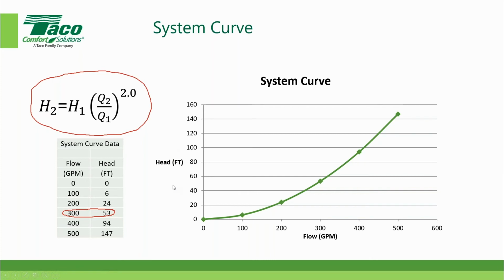If I plot that, I start with my design operating point, the 300 gallons per minute at 53 feet. I use this equation in the upper left-hand corner, I create the table, and then I just plug in these values, and I wind up with this curve, which is called the system curve. In our example, the system is a closed loop pressurized system. Therefore, because it's a closed loop pressurized system, it starts at 0 flow and 0 pressure, and it is actually the right half of a parabola. So that's what a system curve is all about.